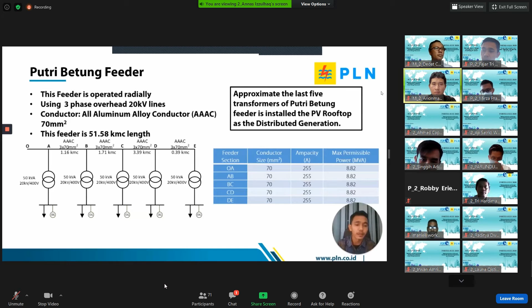For the hosting capacity calculation, we observe the load from all of these transformers that can be shown in the table, both reactive and active power, and both the max and minimum power. Sections A and E have the greatest value from the sections. The left table is the consumption data for each section of the feeder, both the maximum and minimum consumption. And then from equations 4 and 5, we can elaborate the hosting capacity and determine it into all of these values in the right table.